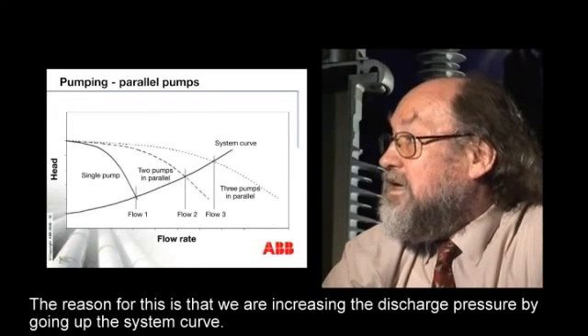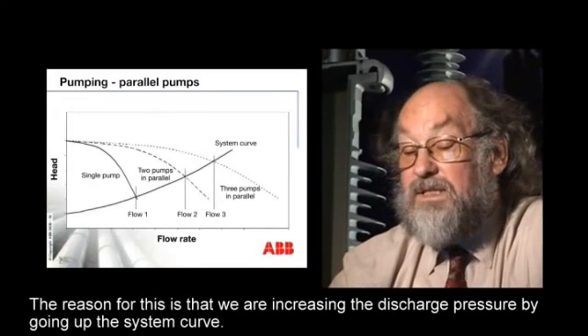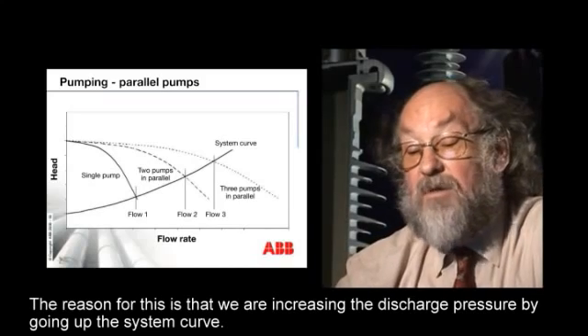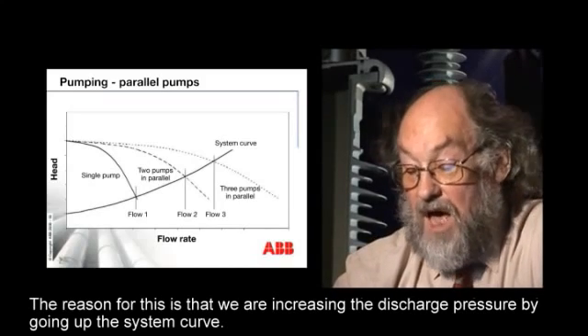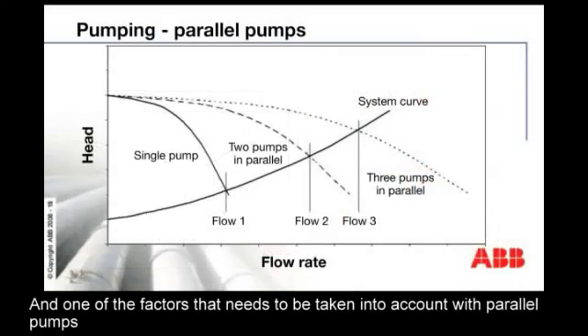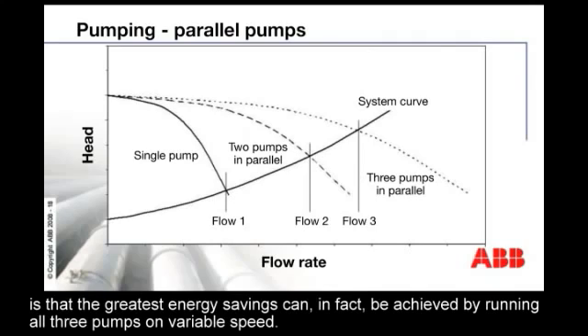Equally, the flow from three pumps in this case is less than the effect of three single pumps. The reason for this is that we're increasing the discharge pressure — they're going up the system curve. One of the factors that needs to be taken into account with parallel pumps is that the greatest energy savings can in fact be achieved by running all three pumps on variable speed.